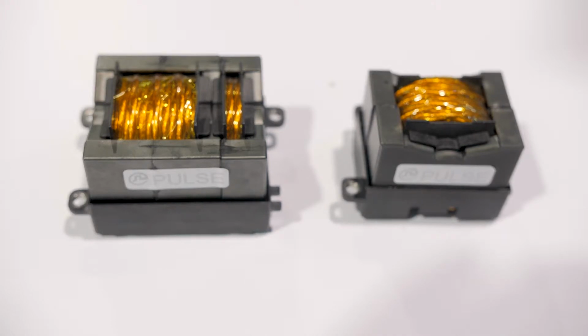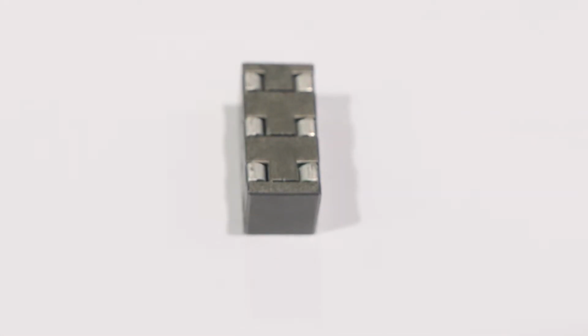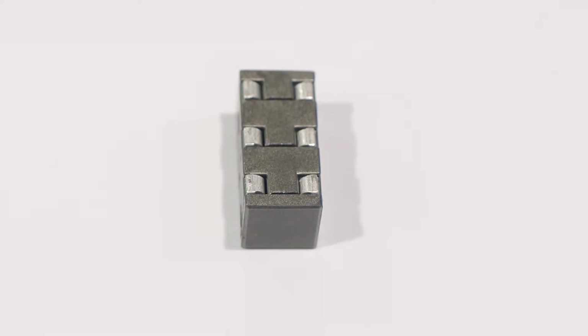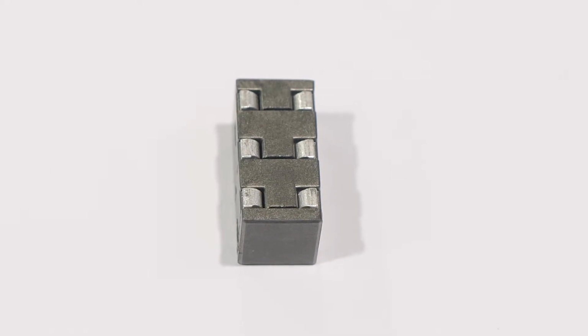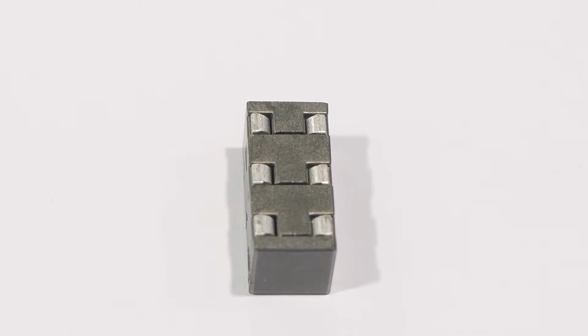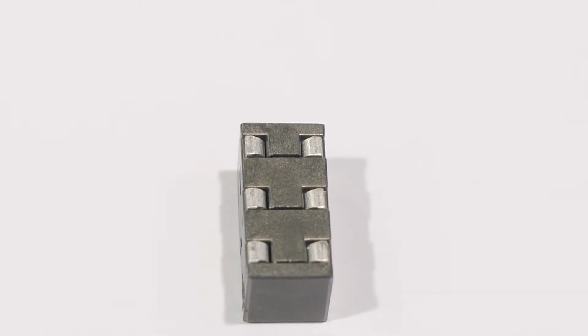So we have a lot of in-house test capabilities to actually measure our components in the real world situations, put the proper waveforms through. We're seeing, as the frequencies get higher, a lot of known phenomena, but things that we haven't had to deal with. So sort of things that you learn about, but haven't had to actually worry about. So fringing losses within the transformer, proximity effects that maybe are not as important at low frequency, but as you get those frequencies up, become very critical.